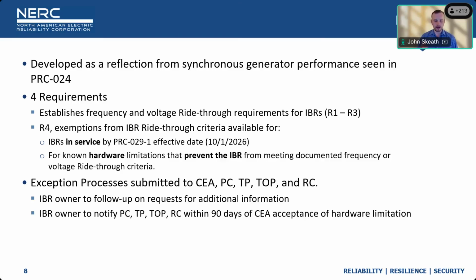And it only is, sorry, I should say the notification is to give the planning entities, your planning coordinator, transmission planner, and your operating entities, transmission operator, and a reliability coordinator, that this particular plant is known to not meet the entirety of the ride-through expectation, so that way all planning and operating entities are aware that the ride-through performance of this particular plant is going to differ from the standardized performance as seen in PRC-29.